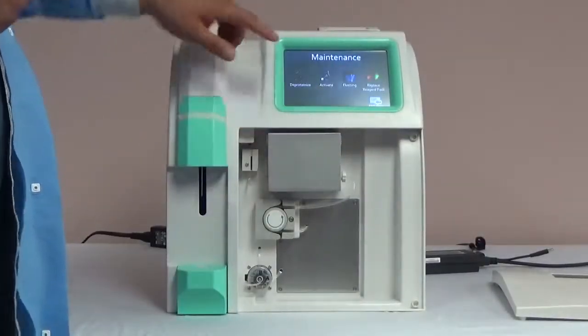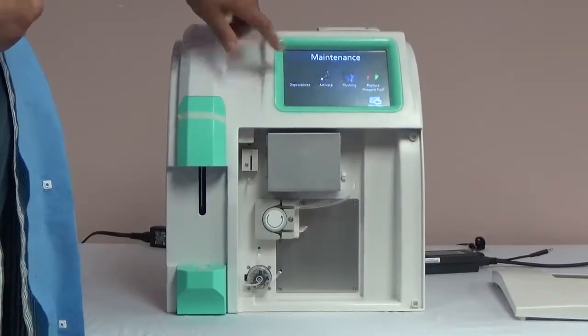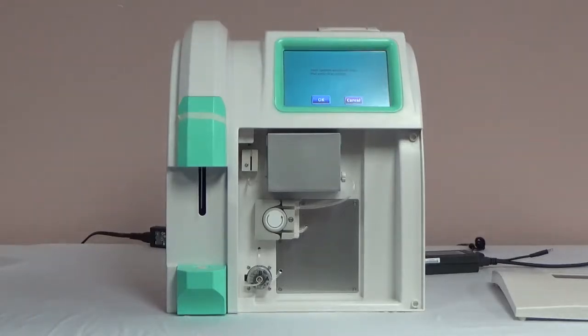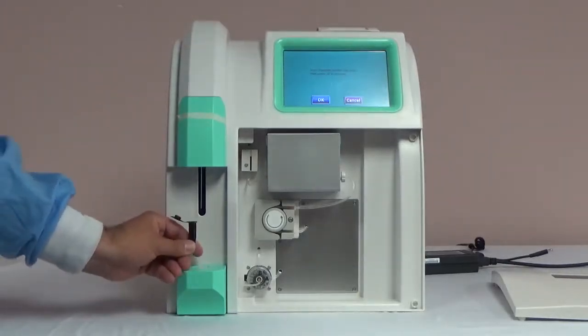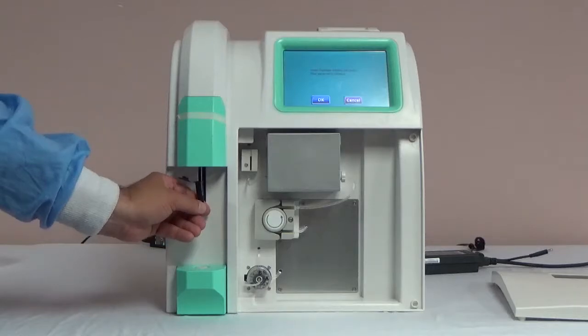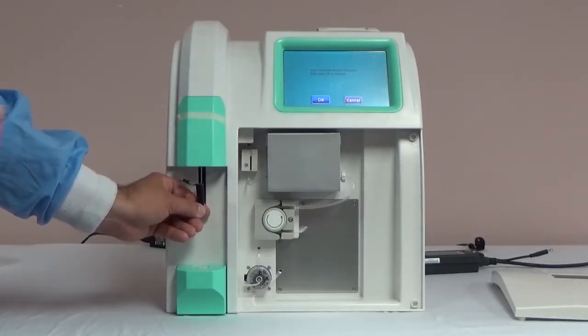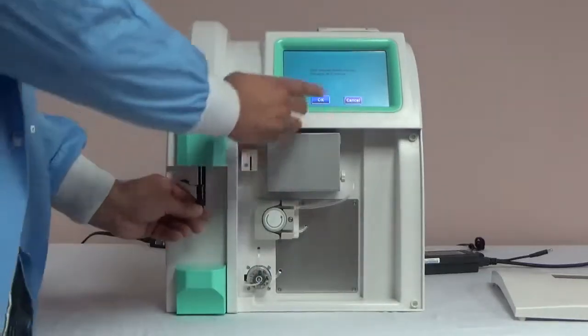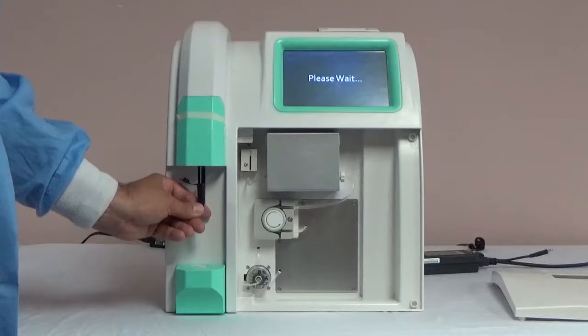After 5 minutes, begin the deproteinization process by selecting Maintenance from the main menu, followed by Deproteinize. The analyzer will ask you to insert the solution into the probe. When you insert the solution, do not push it all the way to the bottom of the vial. If you put the probe too close to the bottom, the probe will not be able to aspirate enough solution. Once it aspirates, the analyzer will tell you to remove the solution and it will run the process.